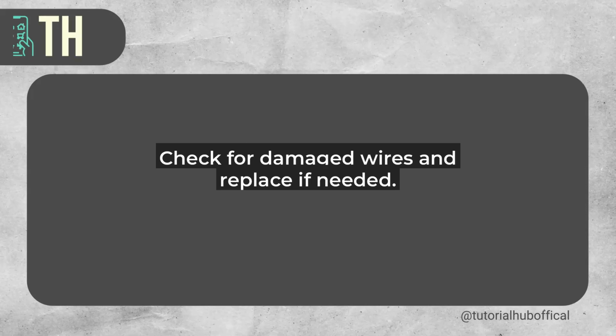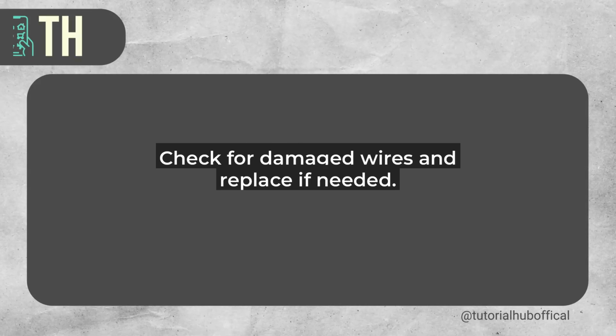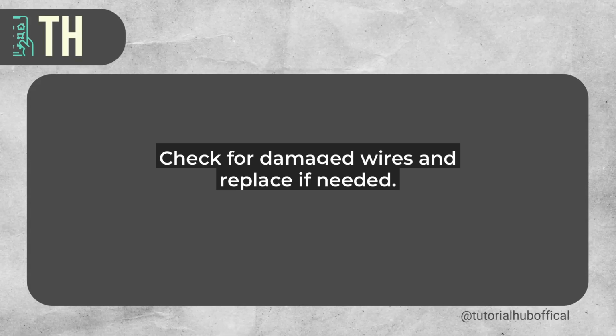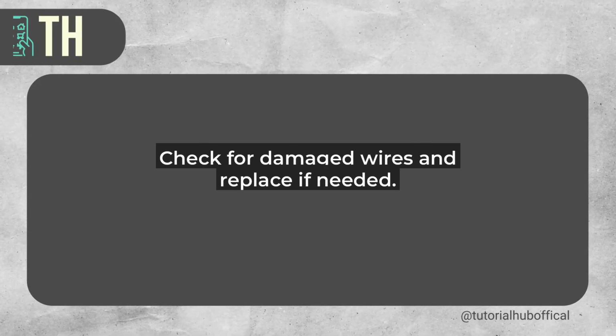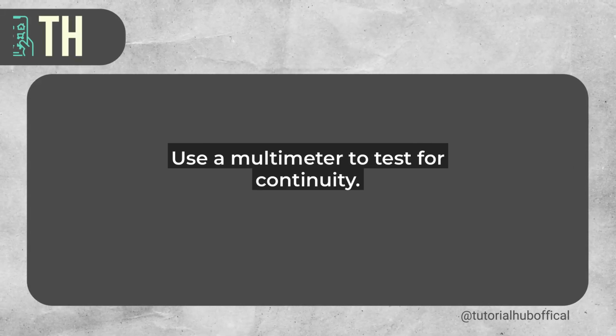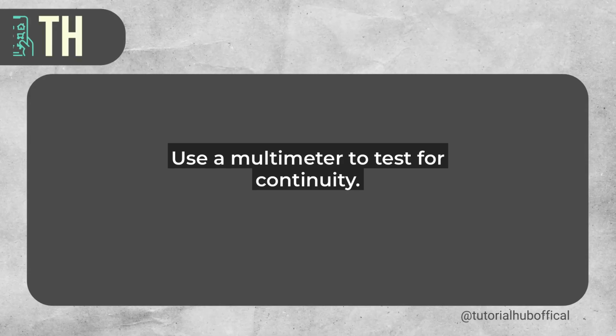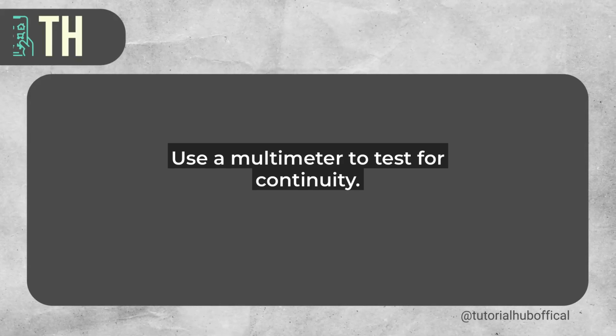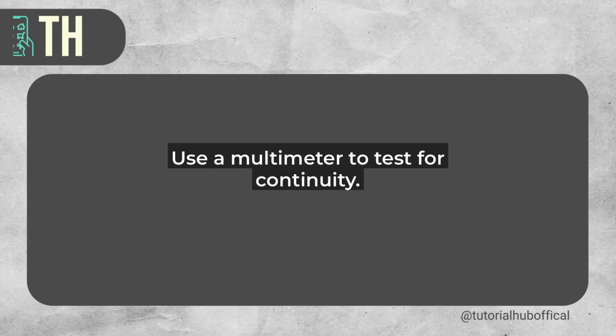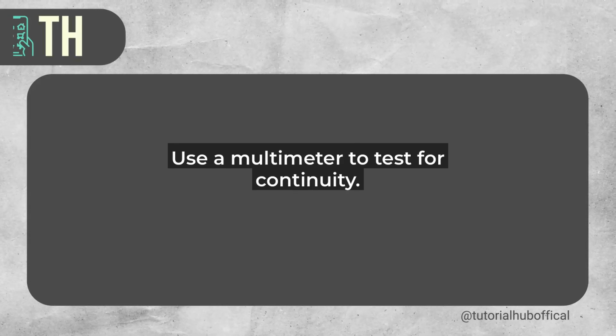Next, inspect the wiring connections between the indoor and outdoor units. Make sure all cables are securely plugged in and free from damage. If you find any frayed wires, you'll need to replace them, safety first. Use a multimeter to check for continuity and ensure there's no short circuit.